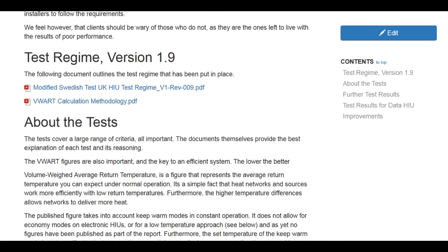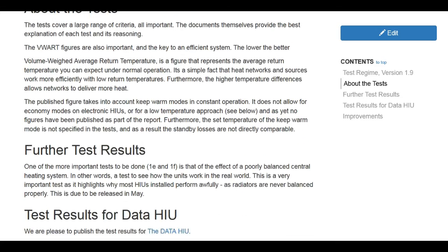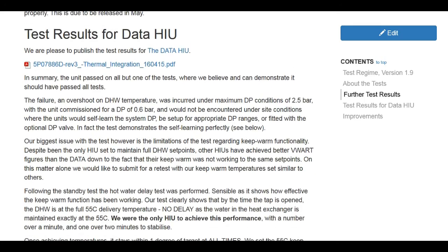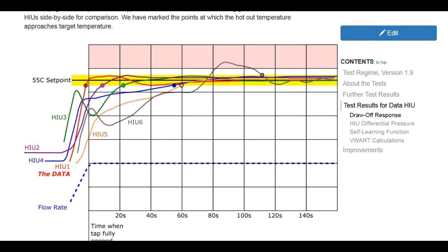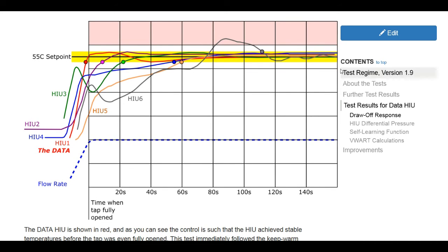Now they're quite detailed tests, so we won't go through them individually here, other than to scan to a few graphs which will show you how the data HIU performed next to other well-known brands on the market. Now the test shows a hot water draw-off test coming out of keep warm mode. So it's basically a tap opening, the flow rate increasing as the tap is opened, and then leveling off and the tap is left running at the same flow rate throughout the test.